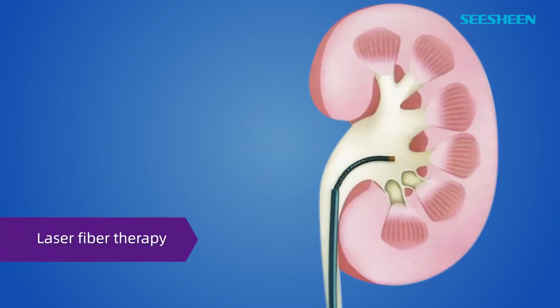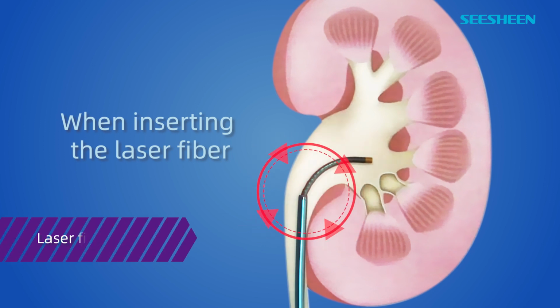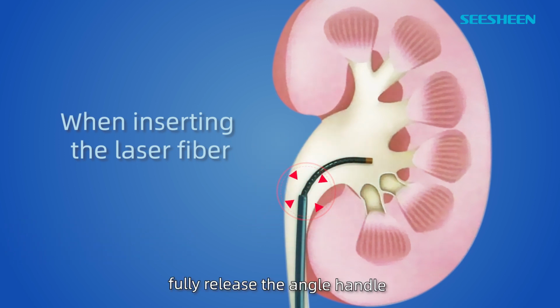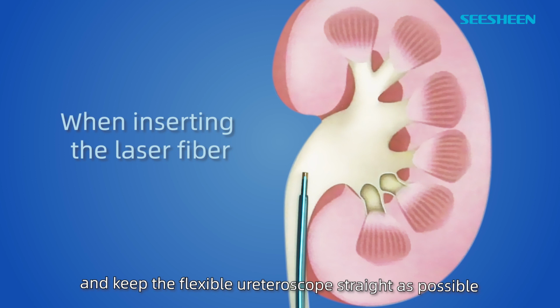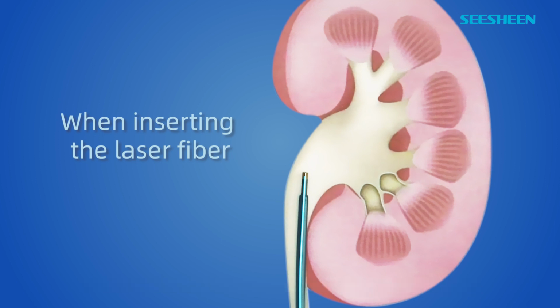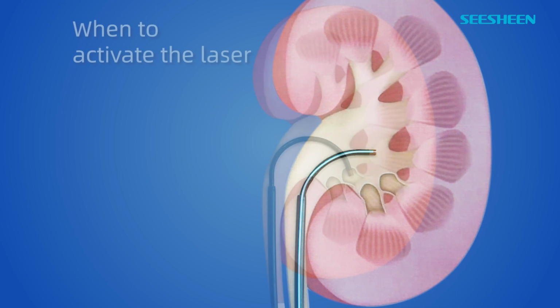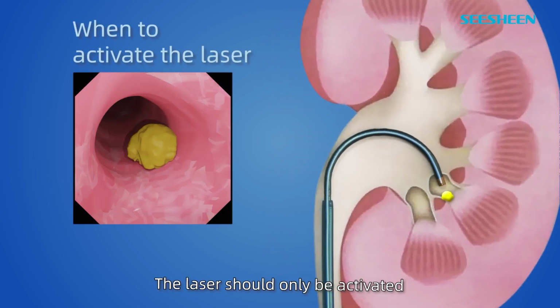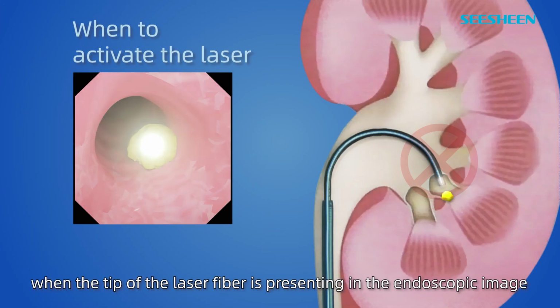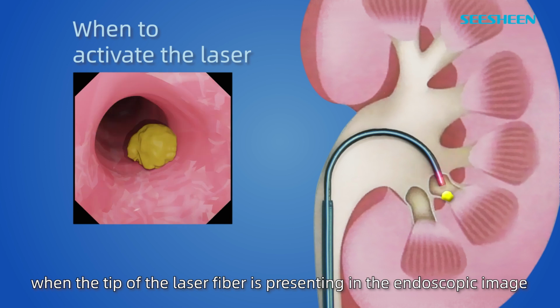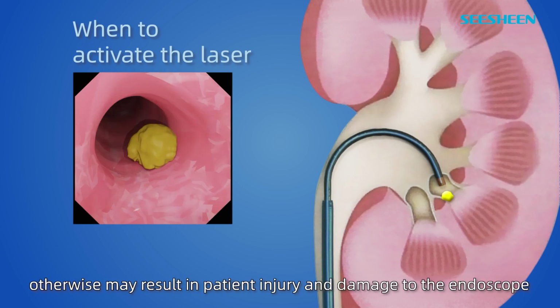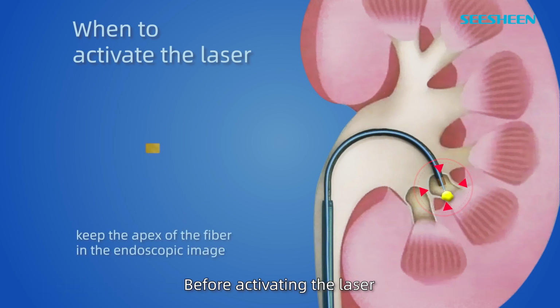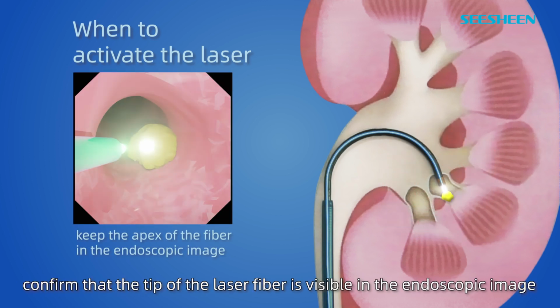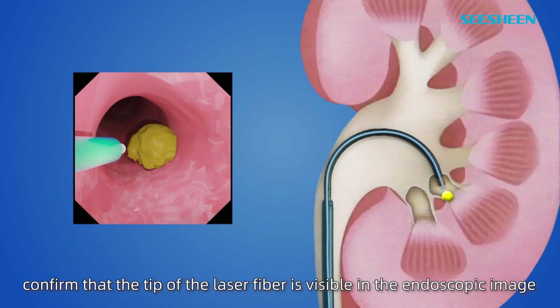Laser fiber therapy. When inserting the laser fiber, fully release the angle handle and keep the flexible ureteroscope as straight as possible. The laser should only be activated when the tip of the laser fiber is present in the endoscopic image, otherwise it may result in patient injury and damage to the endoscope. Before activating the laser, confirm that the tip of the laser fiber is visible in the endoscopic image.